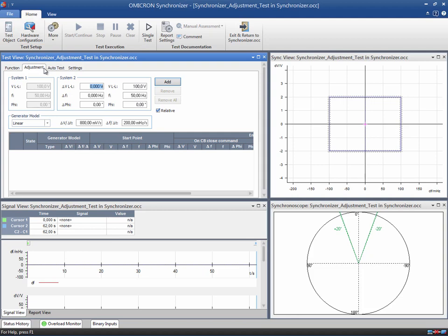The synchronizer test module detects these commands and changes the outputs in accordance with the generator model that has been previously defined. The relay has to issue the control signals until reaching synchronization conditions. During the controlling process, all points are driven to a specific target point inside the synchronizing window. This target point depends on the logic and configuration of the relay.